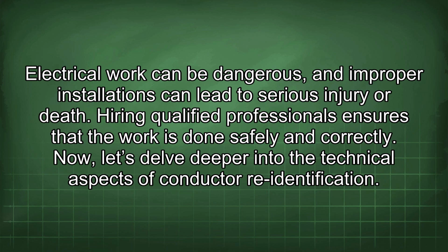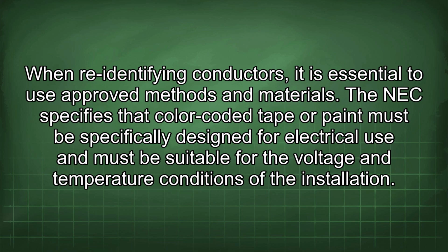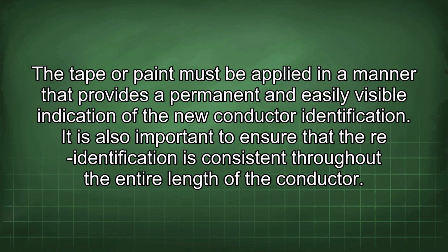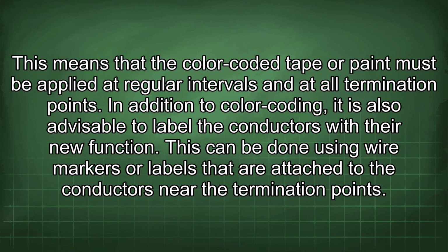Now let's delve deeper into the technical aspects of conductor re-identification. When re-identifying conductors, it is essential to use approved methods and materials. The NEC specifies that color-coded tape or paint must be specifically designed for electrical use and must be suitable for the voltage and temperature conditions of the installation. The tape or paint must be applied in a manner that provides a permanent and easily visible indication of the new conductor identification. It is also important to ensure that the re-identification is consistent throughout the entire length of the conductor. This means that the color-coded tape or paint must be applied at regular intervals and at all termination points.